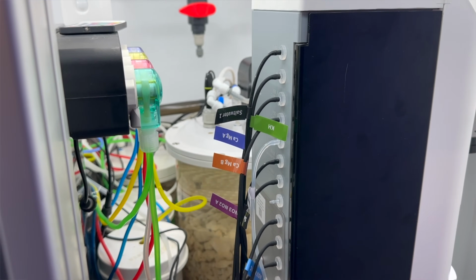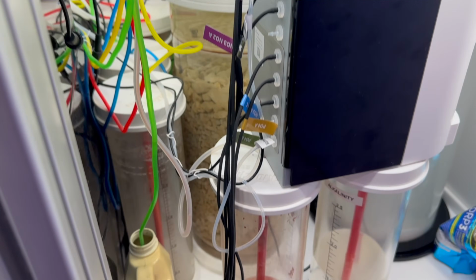All right, guys, that is all of your questions. We'll wrap things up with my pros and cons, and then I will leave you with it. We might start off with the cons because, as you know, on this channel, I always like to finish on a high. So our first con, or downside, if you will, for this machine is the fact that the reagents are mounted externally to the machine itself. So you have this huge spaghetti of tubes coming out of the back of the machine. That may not bother you at all.